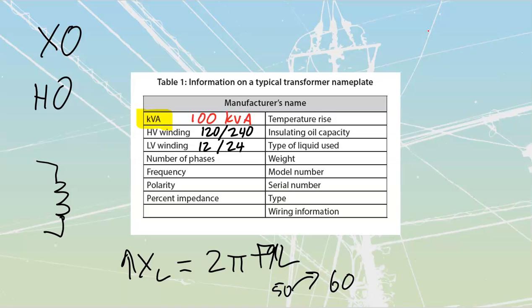Model and serial numbers under the CSA designation. They're the ones who choose which equipment is allowed to be used and which isn't. There has to be model and serial numbers so that they can be tracked, so they can make sure that this was something that was actually approved. Type is sometimes going to be written on there. They don't always write what the type is. If it's specifically for signaling only, then they'll put it on there if it's part of a specific system. You can't just take any old transformer and put it into a fire alarm system. They want to use components that they've got full control over so that they know it's going to meet their minimum standards. Last of all, wiring information.